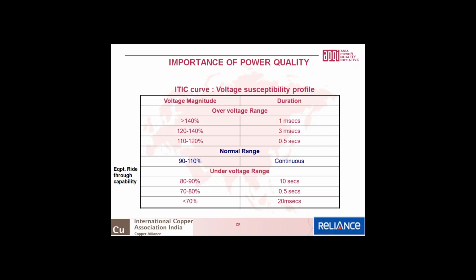And that is the reason why I appeal to the users that whenever you are buying electronic equipment, you must specify what is known as the ride-through capability. That means that even if some voltage dip occurs on the supply side, your equipment should be able to ride through these voltage dips and then come back when the supply is restored. And this ride-through capability time should be at least around 200 to 300 milliseconds, so that it really comes back. You cannot expect 100% supply.